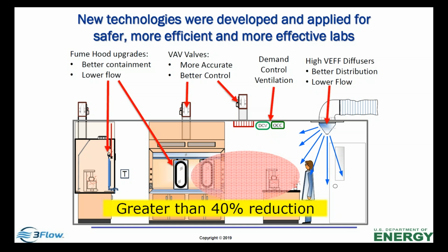The other thing this does for the fume hood retrofit kit is not just save money. I mean, that's a big deal, saving money with the fume hoods. But the other thing it does is it frees up capacity. In a lot of the older buildings around the country and lab buildings, capacity becomes a real issue. So for every 2 hoods you retrofit, you can put either a new high performance hood in or a new standard hood. VAV valves themselves are becoming better, if you will. There've been some enhancements in the industry.